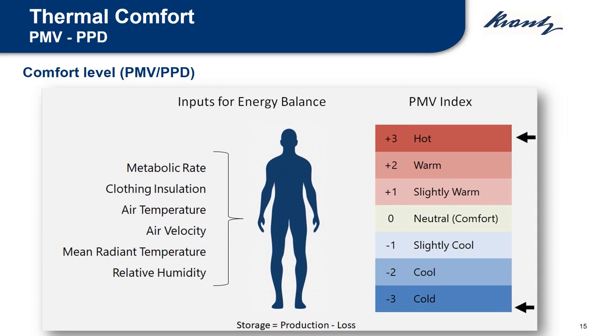Predicted mean vote (PMV) is an index that predicts the mean value of the thermal sensation votes through self-reported perceptions of a large group of people on a sensation scale expressed from -3 to +3 and corresponding to the categories cold, cool, slightly cool, neutral, slightly warm, warm and hot. PMV calculations require the following inputs: metabolic rate, clothing insulation, air temperature, air velocity, mean radiant temperature, and relative humidity.